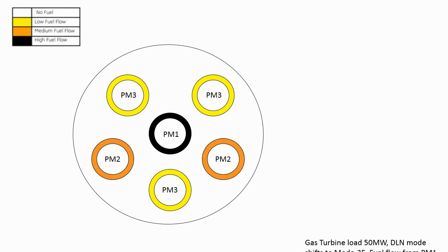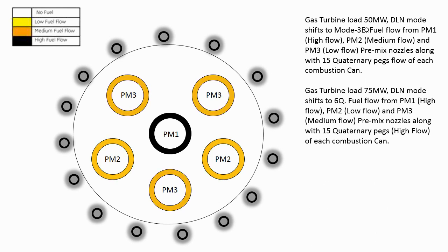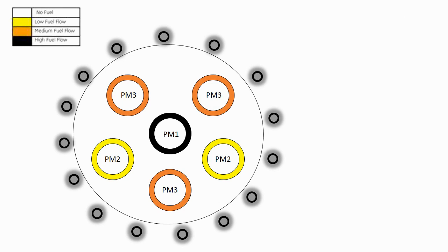When 7FA gas turbine load reaches 50 megawatt, DLN mode shifts from mode 3E to mode 3EQ. Fuel flows from PM1, PM2, and PM3 of each combustion can along with 15 quaternary pegs. Note that fuel flow is high from PM1, low from PM2, while from PM3 fuel flow is medium. There is another way of DLN tuning settings after DLN mode 3E with enriched quaternary fuel injection to stabilize the flame.